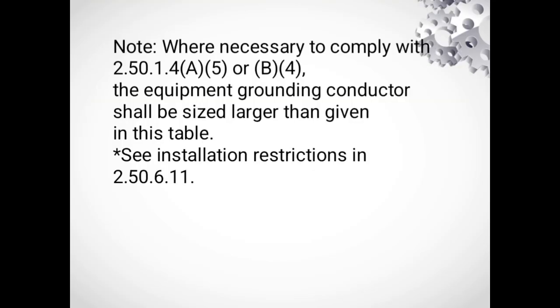Note: where necessary to comply with 2.50.1.4a 5 or B4, the equipment grounding conductor shall be sized larger than given in this table. See installation restriction in 2.50.6.11. Wire sizes. Specific tables like table 2.50.5.13 dictate the correct size of grounding and bonding wires and jumpers. It depends on the size of the main power wires.